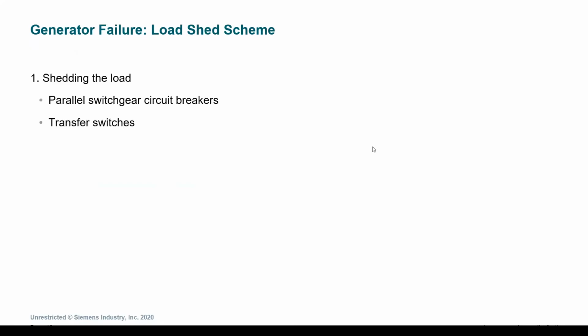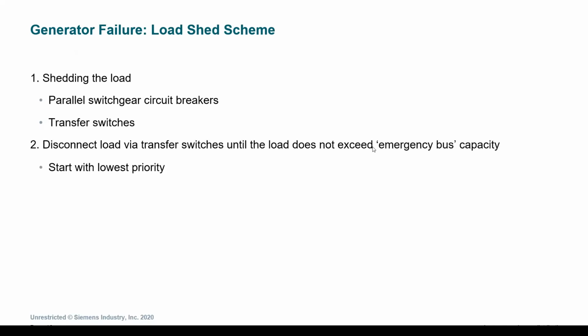So next, we want to look at a proposed load shed scheme. When examining how this system can shed the load, it can be done either through the circuit breakers within the parallel switchgear or through signals sent to the transfer switches. The transfer switches are signaled to disconnect from the emergency position until the load does not exceed the capacity of the emergency bus, and it starts with the lowest priority.